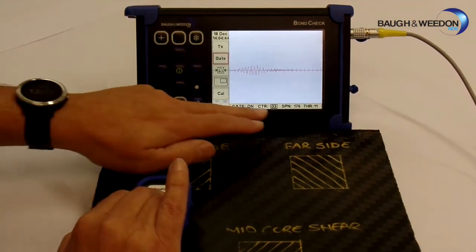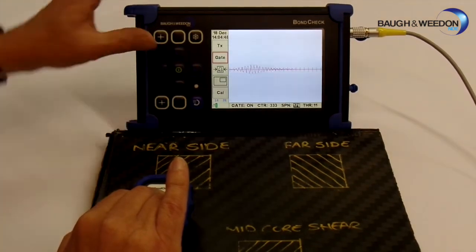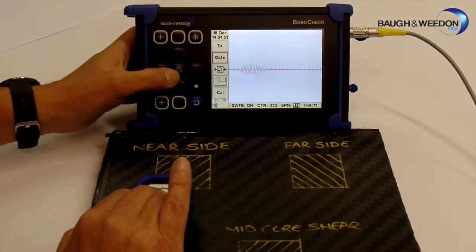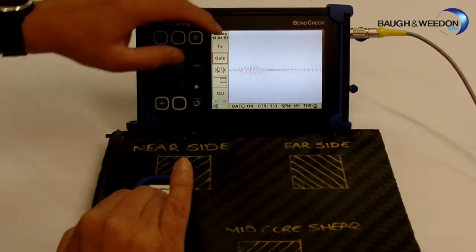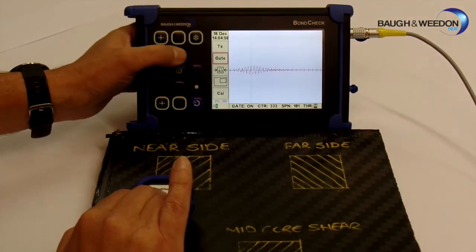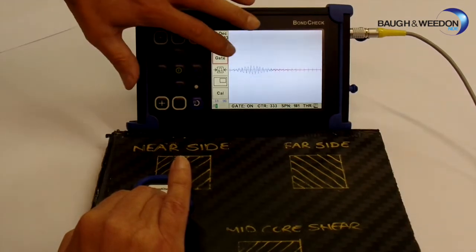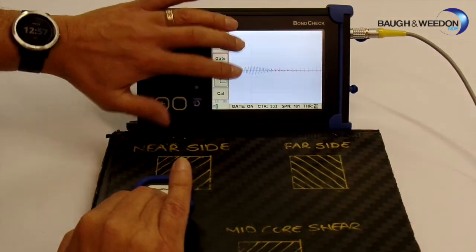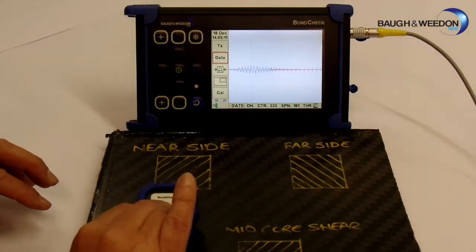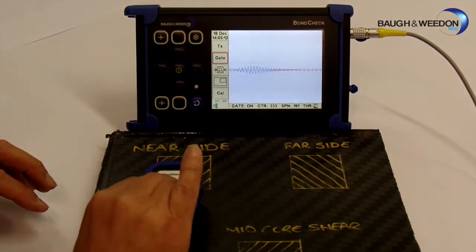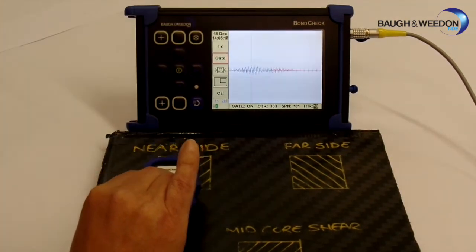So what we now can do is change the span, which is the distance along the waveform, so we can increase or decrease that as required. Or we can go and change the threshold, which is obviously the height of the gates. So if we put it there, if we put it in this area away from the waveform, so it is above it, we can see that the waveform is now blue. So if we scan, nothing is happening. If we go to the defect area, it has broken the gate and the signal has turned red.